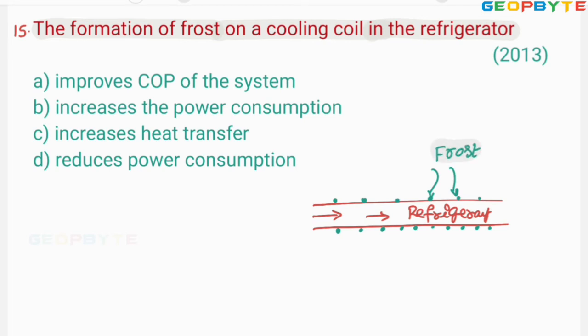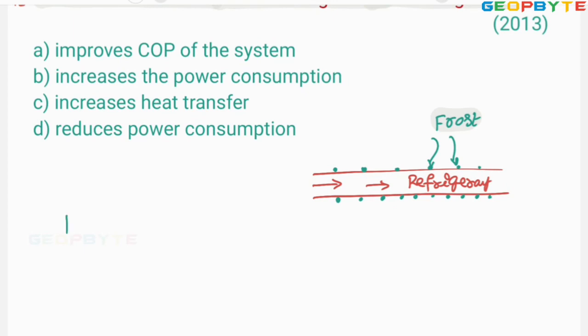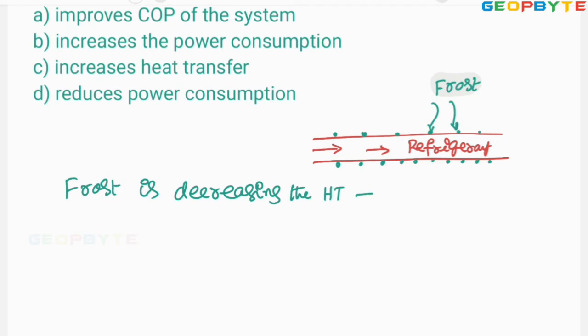Dear friends, remember that frost is acting as an insulator, or frost is minimizing the heat transfer. Frost is decreasing the heat transfer. Once the heat transfer is decreasing, the cooling rate is decreasing. That means the cooling effect or refrigeration effect is decreasing.